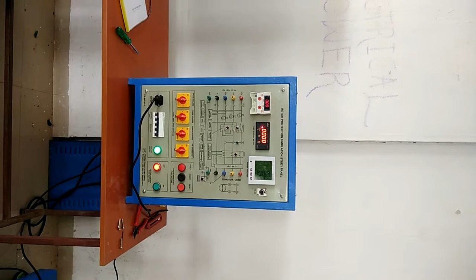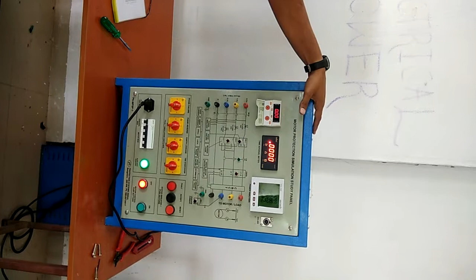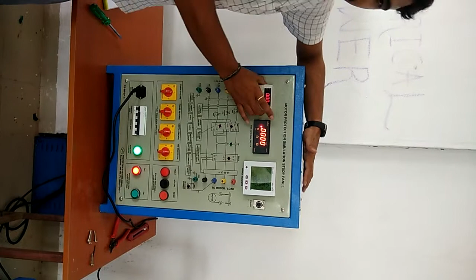So over current, under current, stall, lock, phase reverse, phase failure, asymmetric and ground fault. All of these faults are handled through a single relay. It is called a digital motor protection relay, also called DMPR or EMPR, electrical motor protection relay or digital motor protection relay. And that relay is this. This can protect against over voltage, under voltage, under current, over current, stall, lock, phase reverse, phase failure, asymmetric, ground fault. Okay, these are the things.